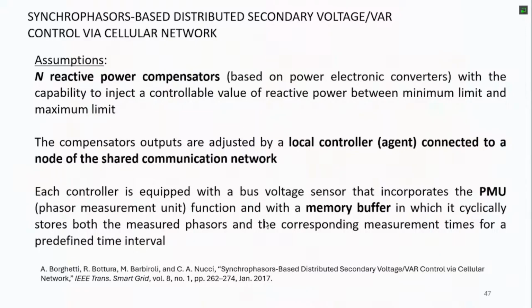So they have also this capability, other than also a memory buffer, so we can store the information in the previous. So assumption and reactive power compensators based on the electronic power converter, for example, the inverters of the PV station, have the capability to inject a controllable value of reactive power between a minimum and a maximum. The compensators output are adjusted by a local controller agent connected to a node of the shared communication network. Is it reasonable?